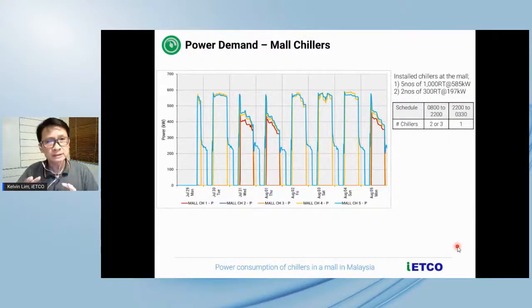So let me share how data helps when you look at a building, when you have visibility. For example, here is real-time data we captured in a shopping mall in KL, where there are 5 units of 1,000-ton chillers installed, roughly 600 kilowatts each operating, and 2 small baby chillers of 300 tons, almost 200 kilowatts of energy used per chiller at maximum. You can see how many chillers are running, how many pumps are running, and at what time. From here we captured information that between 8 a.m. to 10 p.m., 2 to 3 chillers will run, and from 10 to 3:30, 1 chiller will run. Please note this mall has a chiller plant management system installed.